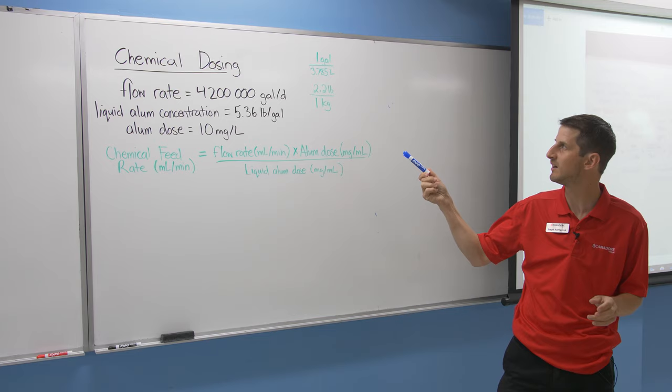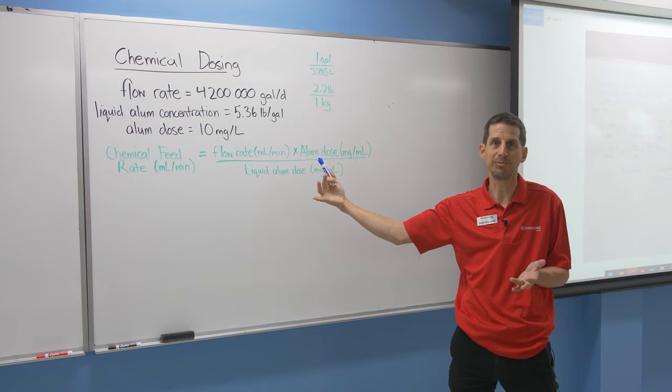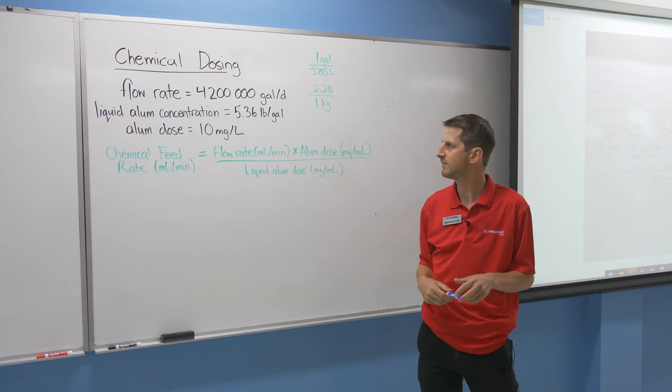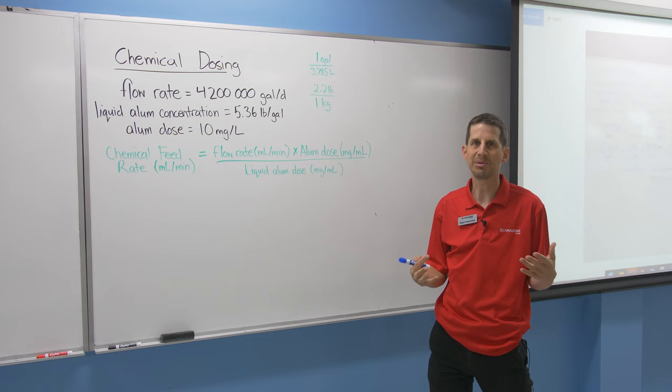In this problem, we've got a flow rate through the plant of 4.2 million gallons per day. We're dealing with coagulation, figuring out what dose to use. Our optimal dose is 10 milligrams per liter, and the liquid alum concentration we're going to use is 5.36 pounds per gallon.